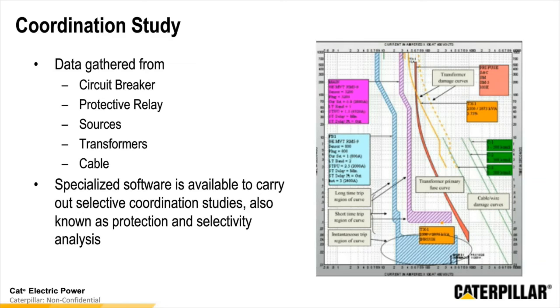You will also, typically, look at the transformers in your systems, and you may have transformer damage curves that you need to apply, or the cables even, because as we look at our protective zones, cables have insulation life, and we want to make sure that we're taking that into account when we look between our different protective zones so that we're protecting the cable as much as we're protecting the entire system. So this can become a very complicated process.